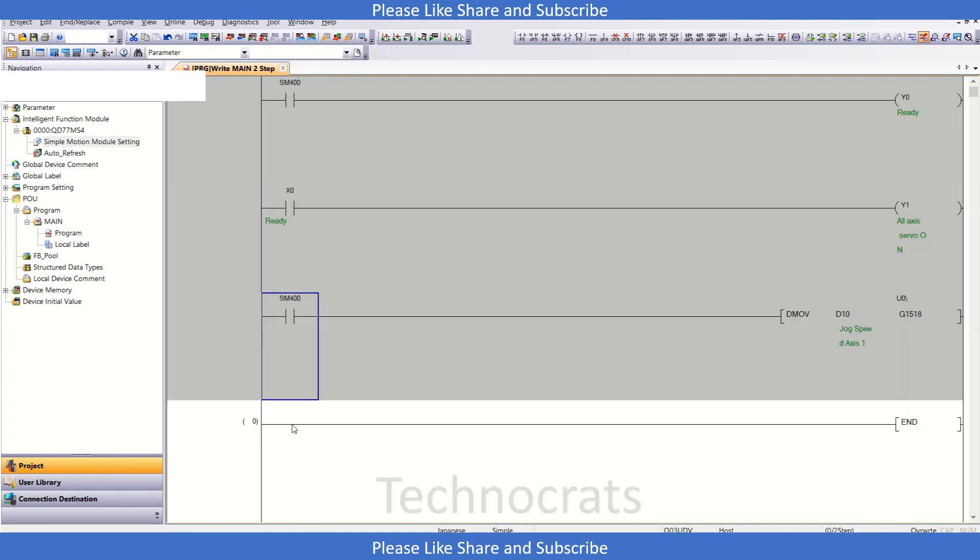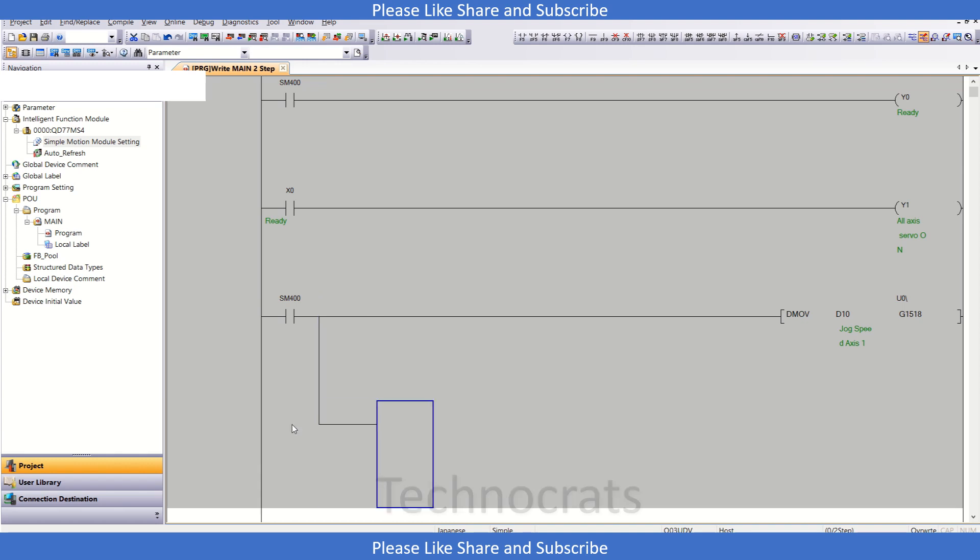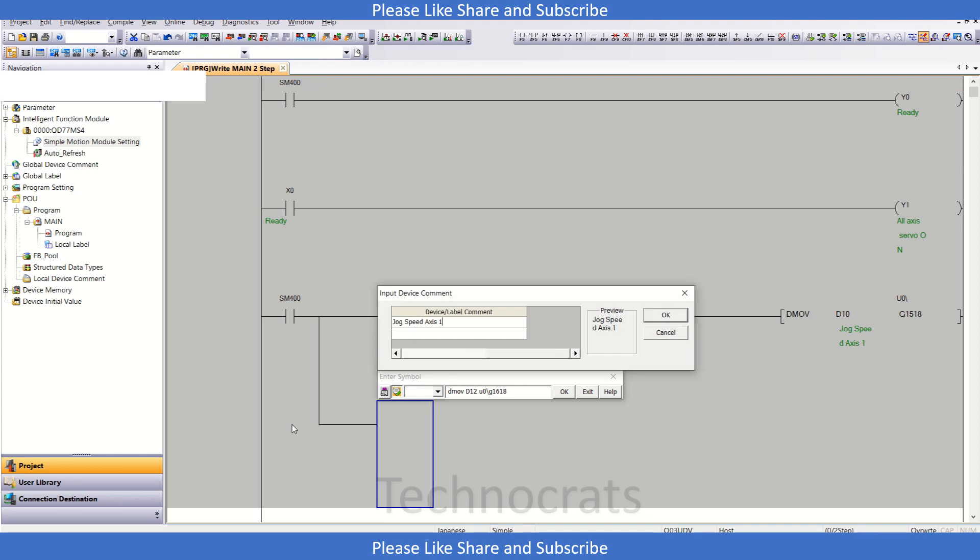For axis number 2, the jog speed buffer address is G1618. So we write: DMOV D12 U0\G1618. This sets the jog speed for axis 2.